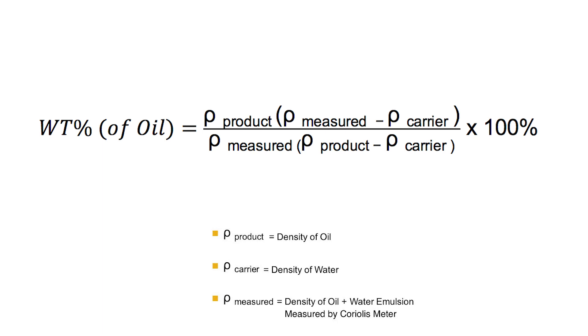For computing net oil flow rate, accurate measurement of density is of paramount importance, which is governed by this equation. Based on this equation, let's see an example of how entrained gas in an oil-water emulsion will report incorrect net oil flow.